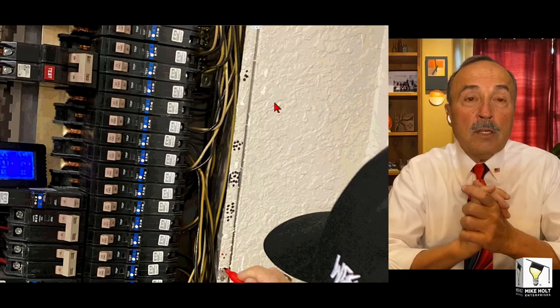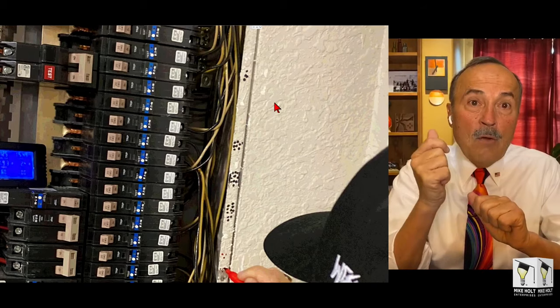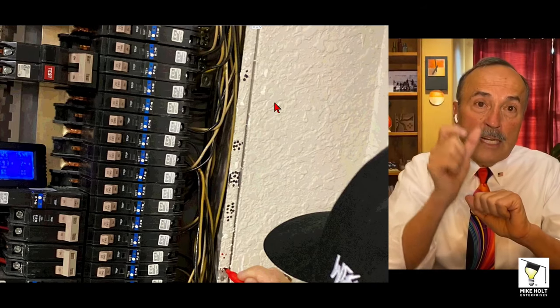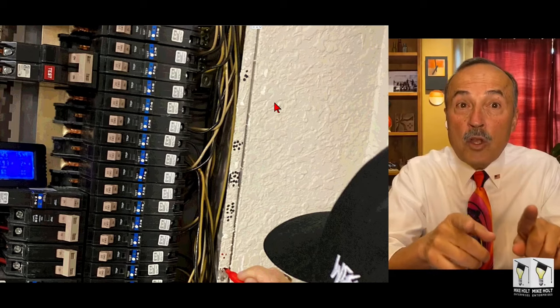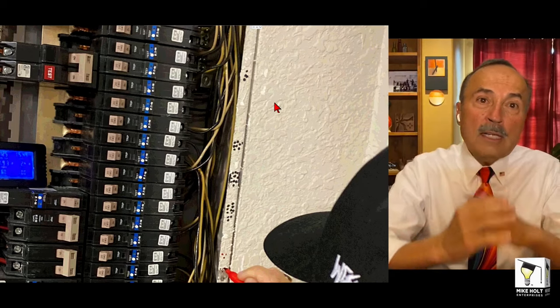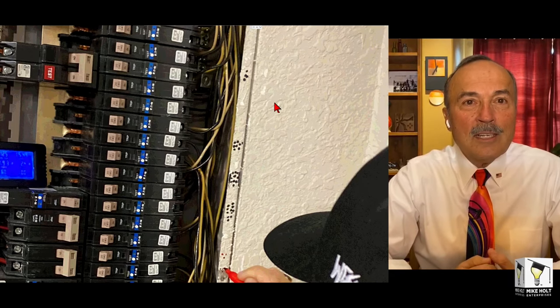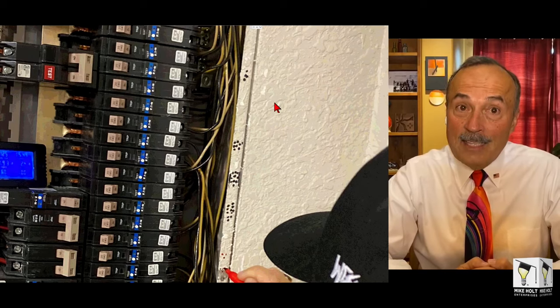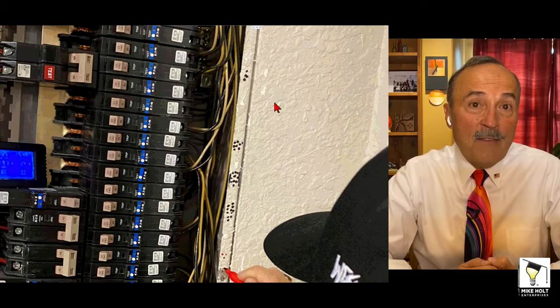So what do I do? The breaker's tripping, pull that puppy out, take the breaker that was above it, put it in this position, put it back on again, get the new AFCI breaker, put it inside the panel, and guess what? I think they're pretty good right now. So I'm not having a problem.